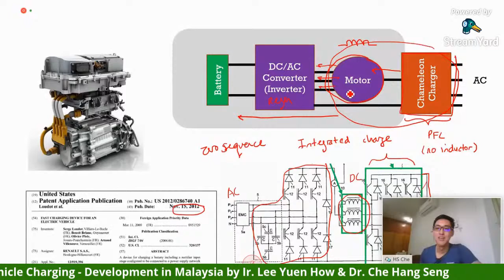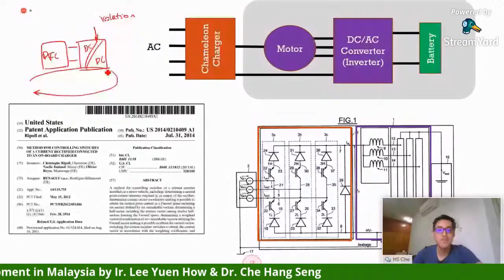But this solution has a setback. The first thing you can see is that, compared with the onboard DC-DC converter, the onboard charger that we see has a power factor corrector connected to a DC-DC converter. This DC-DC converter usually provides some sort of isolation. In electrical systems, isolation of power electronics is good because it prevents leakage current from flowing from the power system to the load. So in this case, on our battery side, when we have switching, there is a chance that leakage current can flow within the power electronics and the ground. So this will trip the RCD, residual current device. So this is not good.